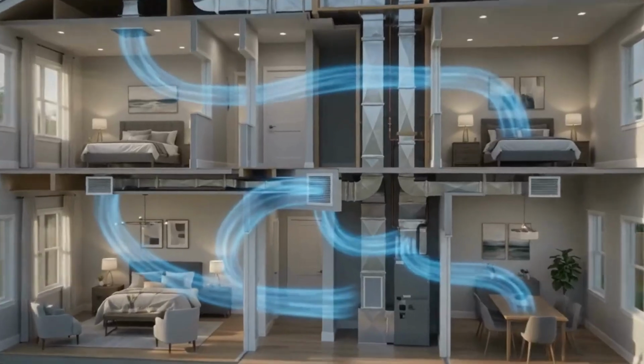Okay, now the other side of this coin is, well, Tom, if I put the filter at the air handler, which is the last point, so even if I have leaks in all my ductwork, all the air is going to come back there and it's going to be filtered before it goes into the air handler. But wait a minute, if I don't have a filter at the grill, isn't that going to mean that all that junk is going to get into my ducts before it gets to that filter? You are 100% correct. It will. So what do we do?